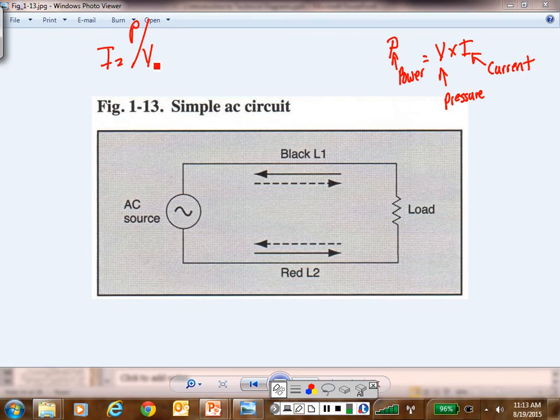Then they came out with an electronic device they call a variable speed drive, which is electronic, it's DC. So they take AC, convert it to DC, then they electronically convert it back to AC to change the speed of the motor. The variable speed drive. It still goes through DC so they can do what? So they can electronically control it. So some people call them variable frequency drives, but they're actually variable speed.